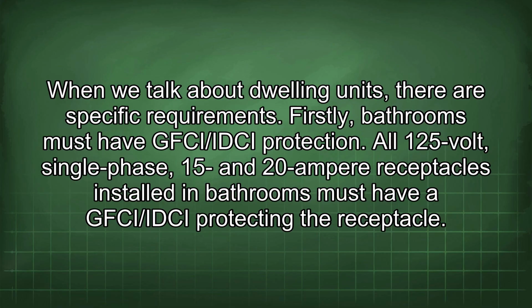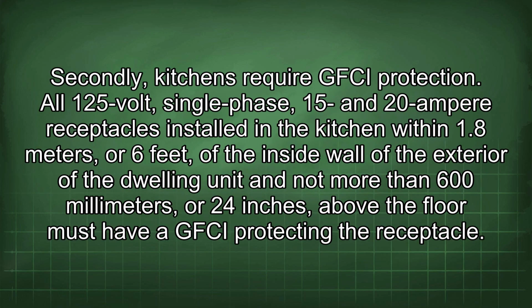Firstly, bathrooms must have GFCI/IDCI protection. All 125-volt, single-phase, 15 and 20 ampere receptacles installed in bathrooms must have a GFCI/IDCI protecting the receptacle. Secondly, kitchens require GFCI protection. All 125-volt, single-phase, 15 and 20 ampere receptacles installed in the kitchen within 1.8 meters, or 6 feet, of the inside wall of the exterior of the dwelling unit and not more than 600 millimeters, or 24 inches, above the floor must have a GFCI protecting the receptacle.